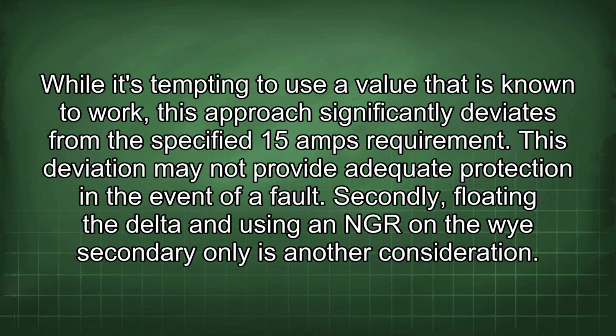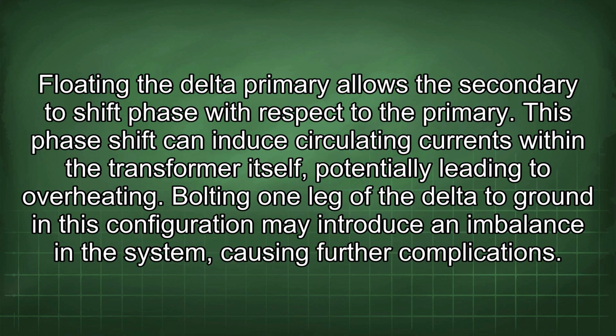Secondly, floating the delta and using an NGR on the Y secondary only is another consideration. Floating the delta primary allows the secondary to shift phase with respect to the primary. This phase shift can induce circulating currents within the transformer itself, potentially leading to overheating. Bolting one leg of the delta to ground in this configuration may introduce an imbalance in the system, causing further complications.